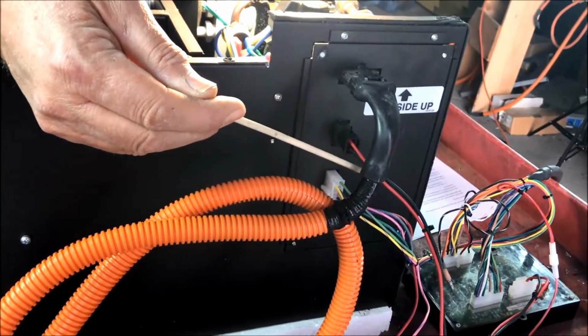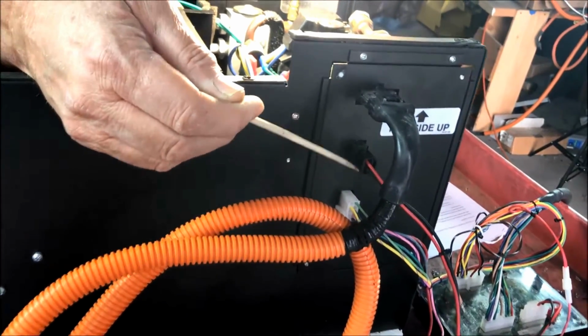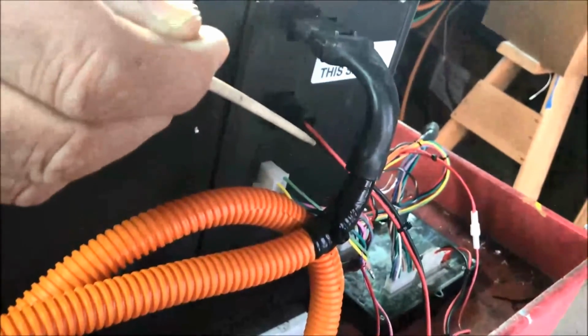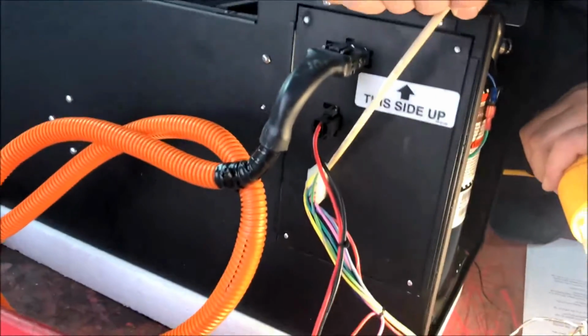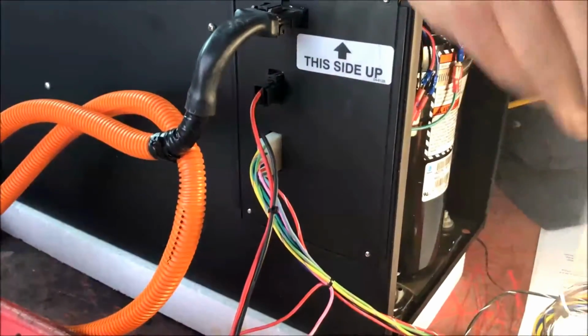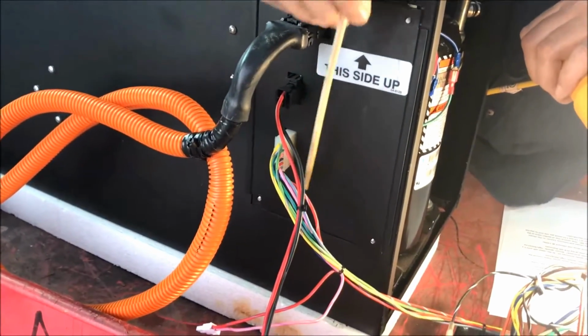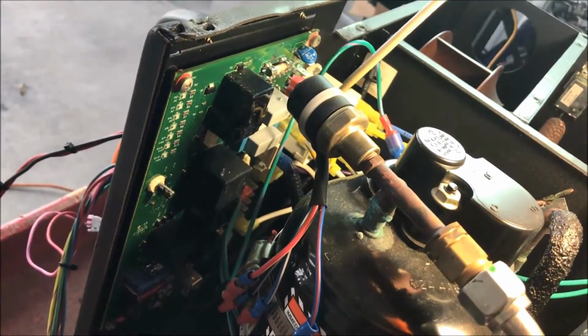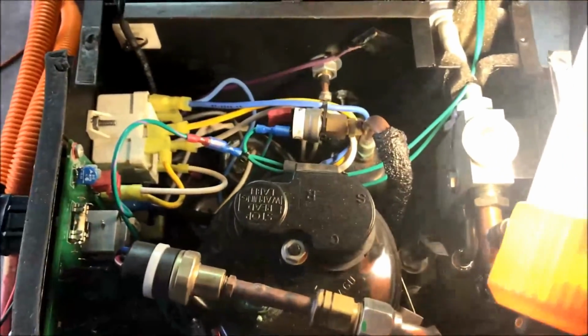It's very important to have 20 amps of available power. If there's any drop in voltage, it will cause problems on the circuit board. The printed circuit board is mounted on the side of the HVAC. It is controlled with DC signals from the ECM. It turns on the compressor, the heater, the blower, the different devices. On this side of the circuit board, the DC signals close relays, which will then conduct 120 volt AC power to the different components.